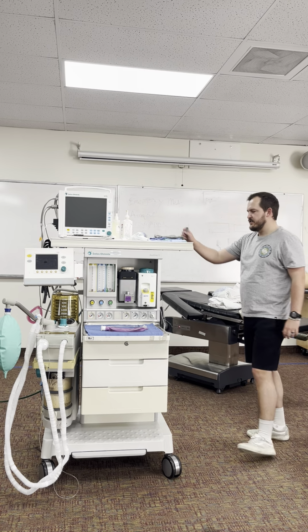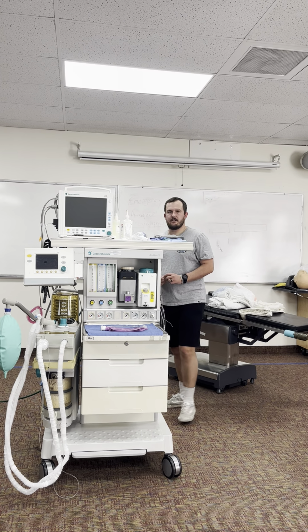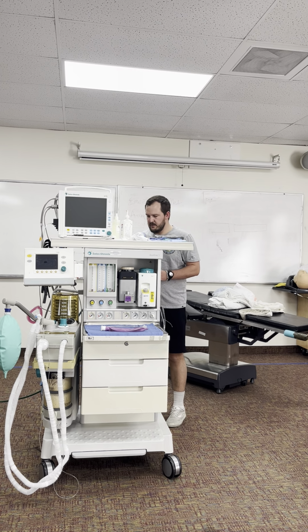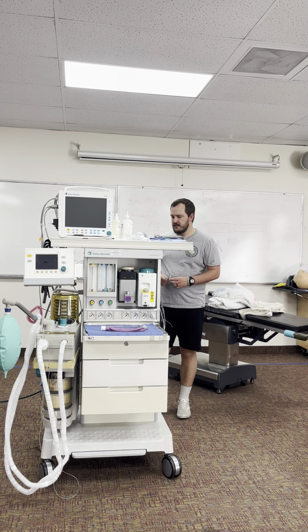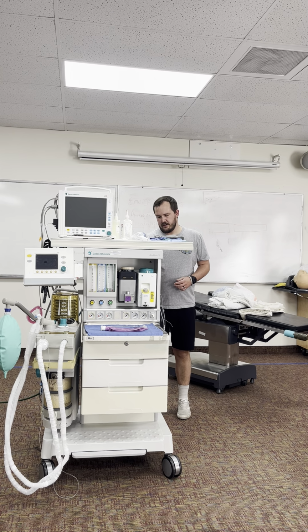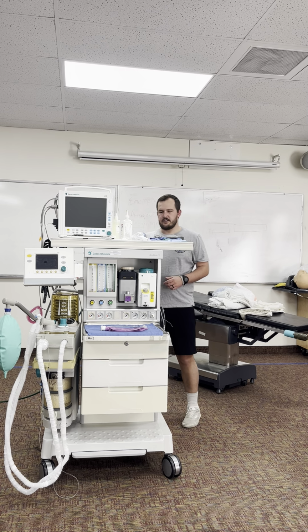So first, when I walk into the OR, I'm going to go to the back of the machine. I'm going to check that I have the appropriate cylinders in the right spot. And then I'm going to open up, starting with my oxygen, leave it open for a couple seconds just to let it pressurize. I do the same with my air and nitrous oxide.